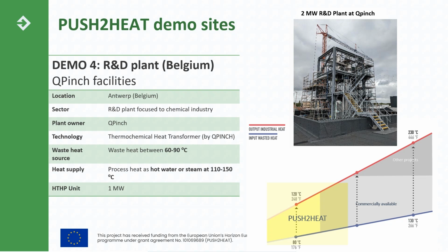But the challenge and objective related to this technology in Push to Heat is to adapt it so that it can work not just from a technical point of view, but mainly to make it successful from an economic point of view too. So, to adapt this technology to lower temperature ranges, appropriate for waste heat sources between 60 and 90 degrees centigrade, and process heat delivery either as hot water or steam, more or less in the range of 110 to 150 degrees centigrade.